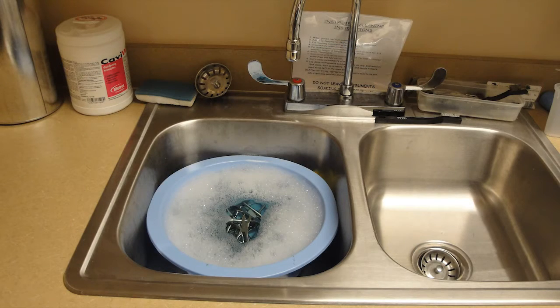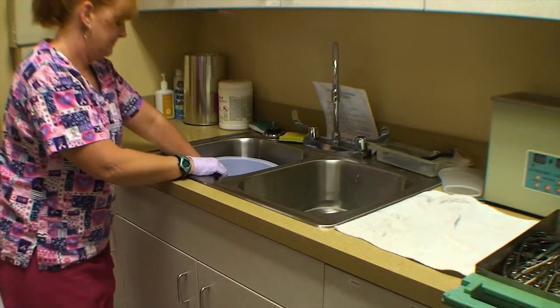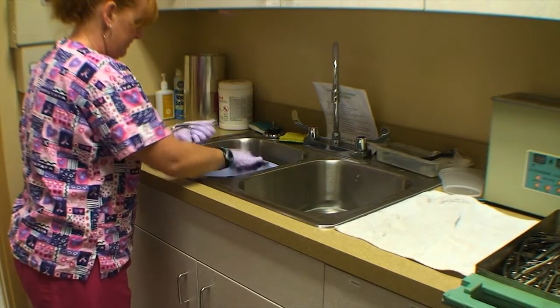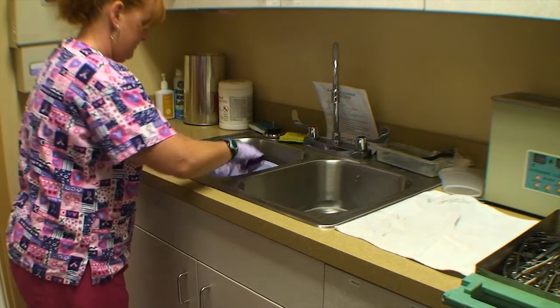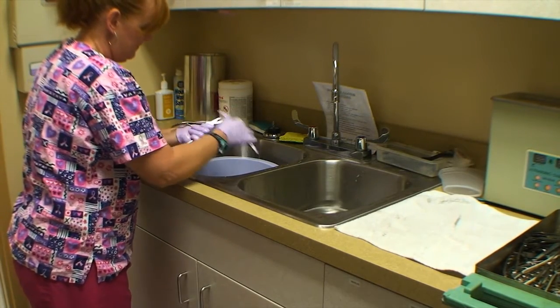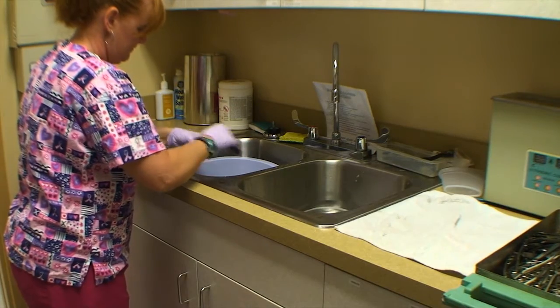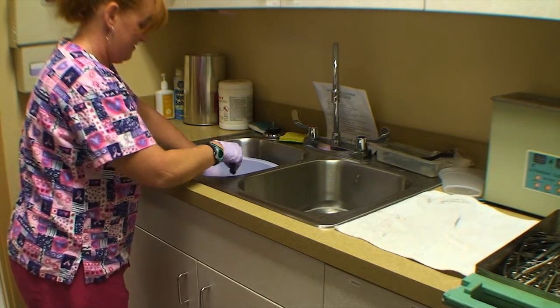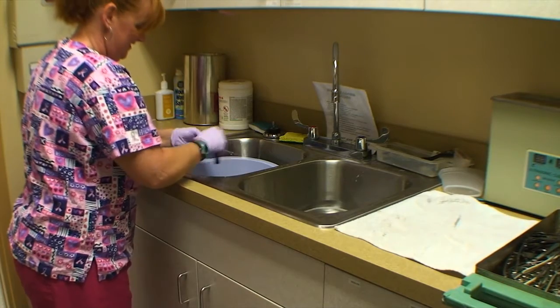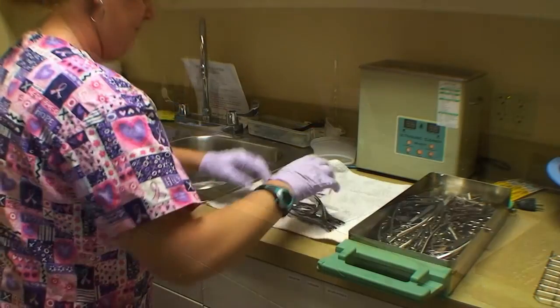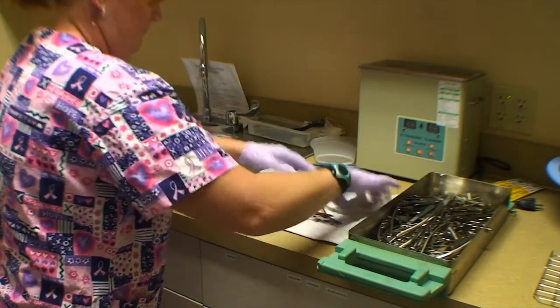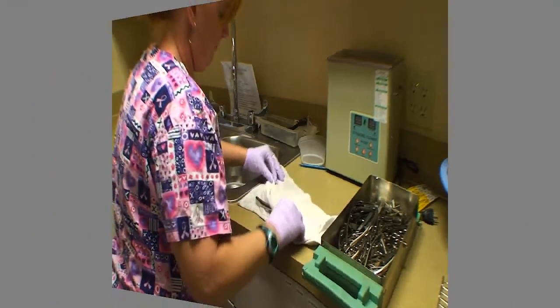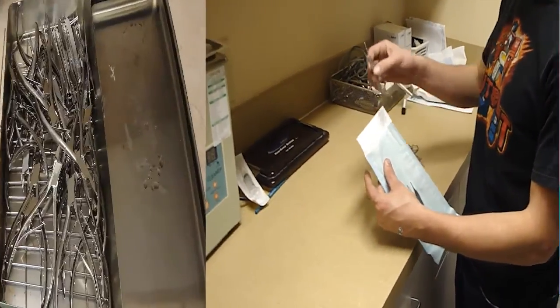Instruments placed in the basin will need to soak for 3 to 15 minutes, depending on the use of the tool and the amount of contamination. After the tools have soaked in the detergent, you will need to manually scrub the instruments. You will find a black-handled brush with white bristles to do this task. Thoroughly scrub the instruments to make sure they are clean and there are no tissue or fluid residues left on the instrument. After you have scrubbed the instrument, you will need to rinse them in warm water and set them to dry for wrapping. Depending on the instrument, you may need to wrap them, or they may need to be put unwrapped in the autoclave.